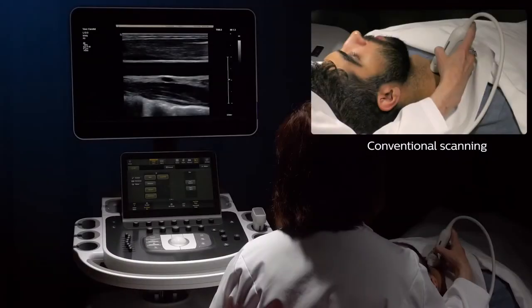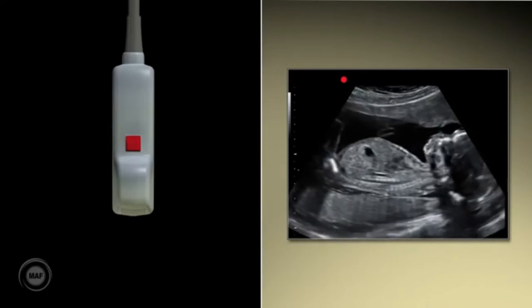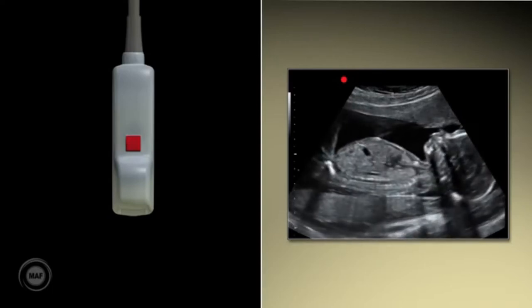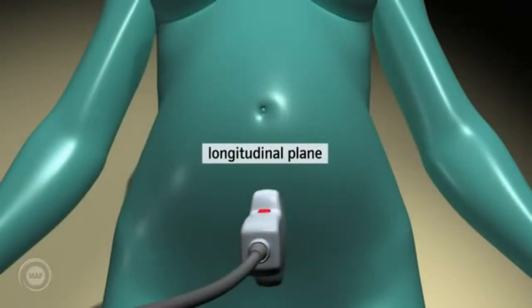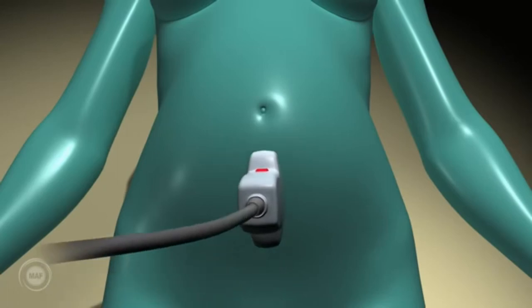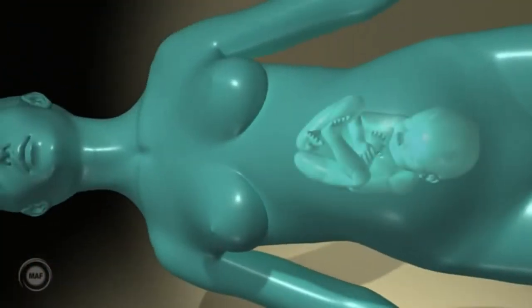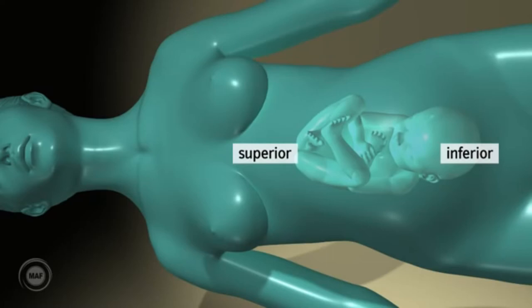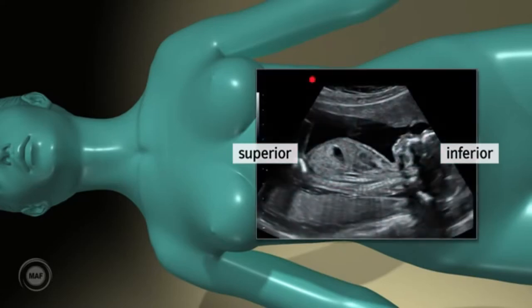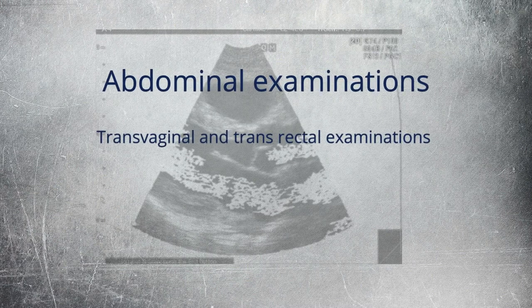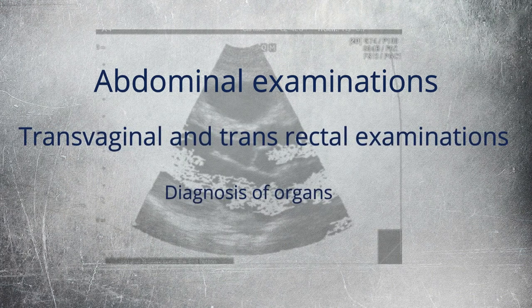The second type of probes are convex probes. The convex ultrasound transducer is also called the curved transducer, because the piezoelectric crystal arrangement is curvilinear. The beam shape is convex and the transducer is good for in-depth examinations, even though image resolution decreases when depth increases. The footprint, frequency, and applications depend on whether the product is for 2D or 3D imaging. The convex transducer for 2D imaging has a wide footprint and its central frequency is 2.5 MHz to 7.5 MHz. It can be used for abdominal, transvaginal, and transrectal examinations, and diagnosis of organs.